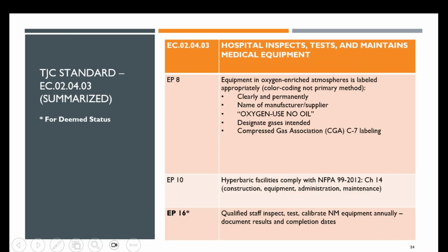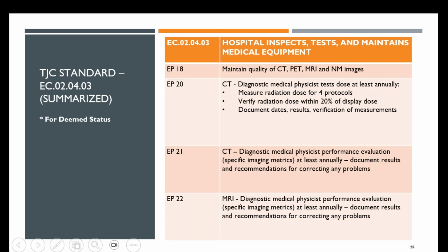All right, continuing on, you're going to need to ensure that equipment listed for use in oxygen-rich environments is labeled appropriately, and if you are a hyperbaric facility, you must comply with NFPA 99-2012, Chapter 14. Deemed hospitals must have qualified staff inspect, test, and calibrate nuke med equipment annually, documenting the results and completion dates. You must maintain the quality of CT, PET, MR, and nuke med images, and the next several are all about medical physicist tasks for certain imaging equipment and modalities, so it might seem a bit redundant, but they do apply over each modality.